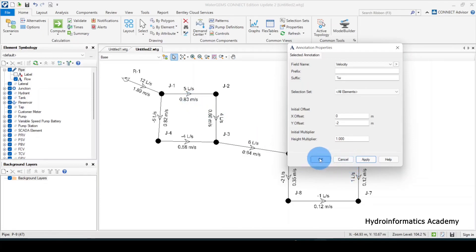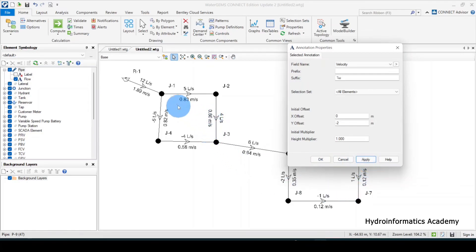Before moving further, I want to start optimizing my model by taking the velocity into consideration. The acceptable range for velocity varies from country to country, but for most cases it is from 0.5 all the way to 1.5 or 2 meters per second. From here, what we are having is 0.6, 0.8, and 1.89.